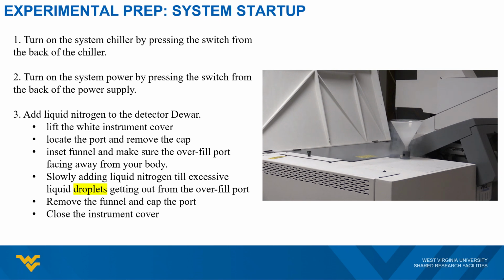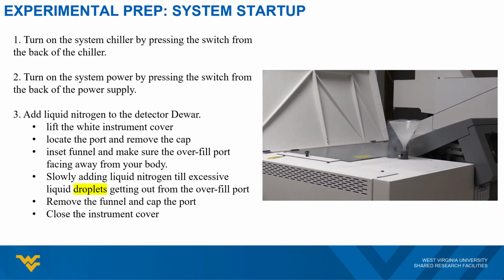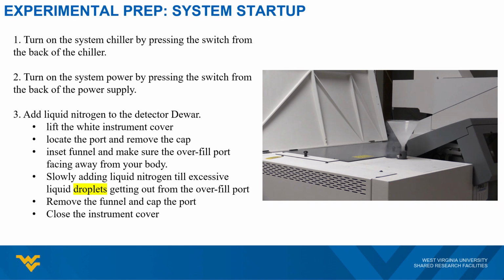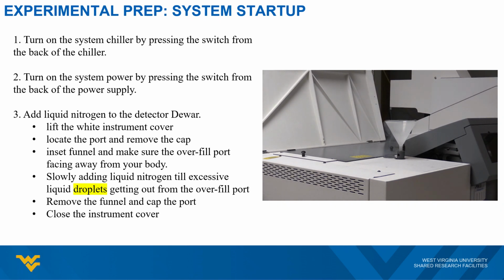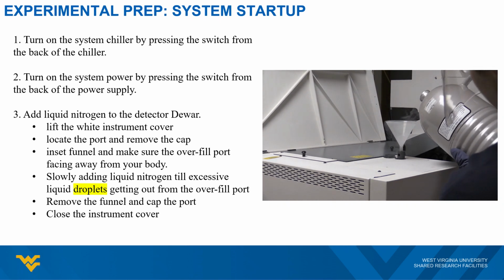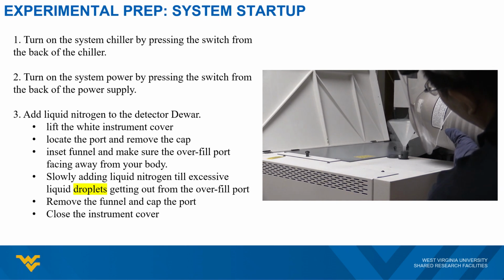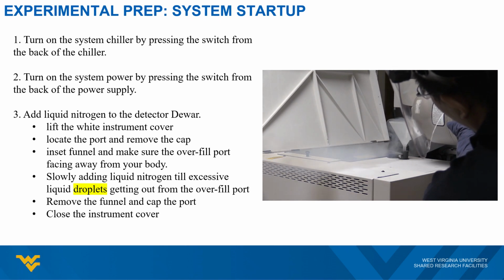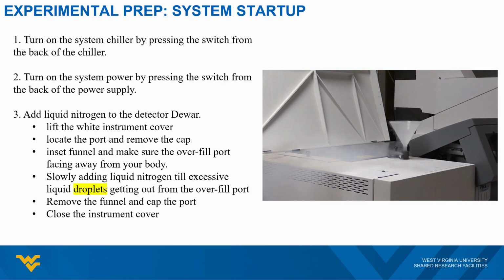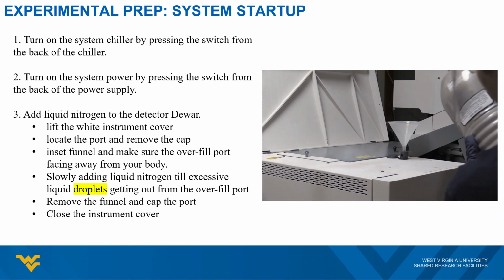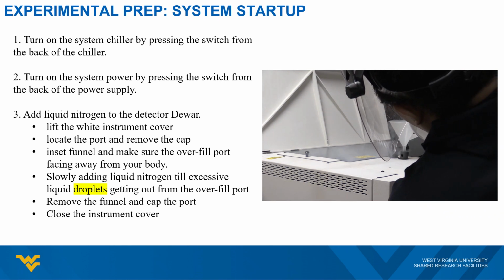I want to emphasize that when we add liquid nitrogen to the dewar at room temperature, the liquid nitrogen will boil off very hard, creating a stream of gas exiting from the overfill port. It's crucial to understand that this gas stream does not indicate liquid nitrogen accumulation. Instead, it's a sign that the dewar is cooling down. Once the dewar is fully cooled, it will start to accumulate liquid nitrogen inside.